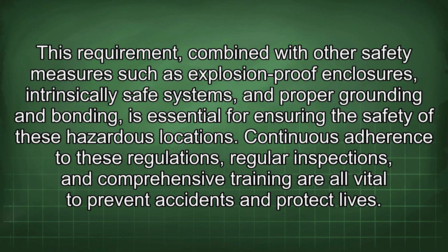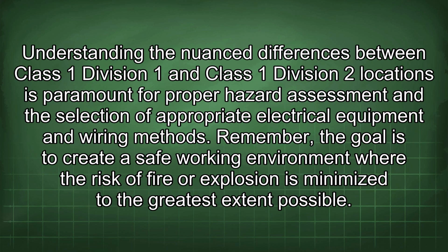This requirement, combined with other safety measures such as explosion-proof enclosures, intrinsically safe systems, and proper grounding and bonding, is essential for ensuring the safety of these hazardous locations. Continuous adherence to these regulations, regular inspections, and comprehensive training are all vital to prevent accidents and protect lives. Understanding the nuanced differences between Class 1 Division 1 and Class 1 Division 2 locations is paramount for proper hazard assessment and the selection of appropriate electrical equipment and wiring methods.